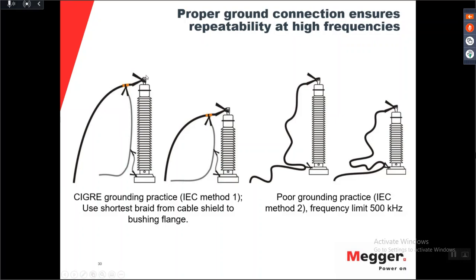It must be tight here, here, and especially here, because you should take a shield ground from the top of the transformer to the bottom ground here. And the connection quality matters very, very much for this one. With connection quality, you should have a tight connection.